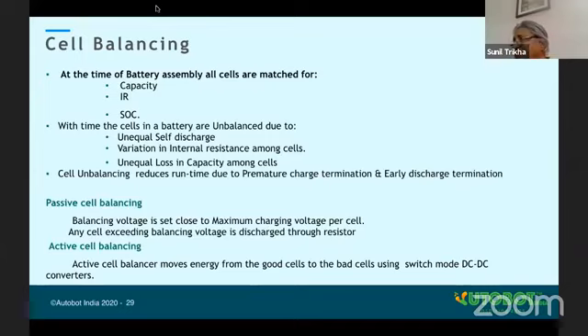There is also active balancing. Active balancing keeps happening every time. It monitors the relative variation among the cell voltages, and keeps correcting time to time. Again, there are methods where there are DC-DC converter circuits on each cell, so the cell with high voltage can pump energy to the cell with low voltage. Since you need quite a big gradient, first there is a DC-DC converter. It selects the highest voltage cell, then boosts the voltage to something around 4.55 volts, and then charges the low voltage cell till both cells come to the same voltage. This is a continuous process, called active cell balancing.